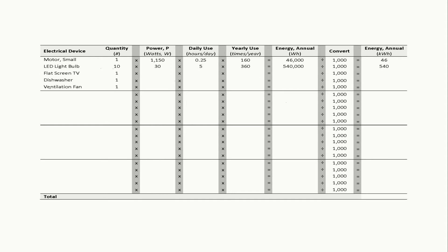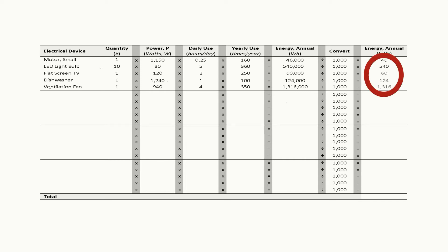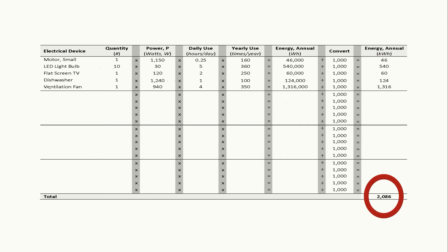You would repeat this process for all other electrical loads, being sure that no device or appliance has been unintentionally excluded. Omitting an electrical load from this inventory could result in the solar electric system being undersized. While DC electric loads can be included in your assessment, they're not relevant when sizing an inverter, since inverters only supply AC power. Adding up all the devices on this inventory provides a total annual energy consumption of 2,086 kilowatt hours per year, and this value would then be used to size your solar electric system.